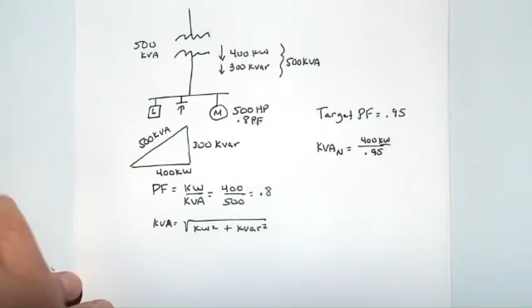My actual new kVA then, kVA new, would be my existing kilowatts, which is 400, because my kilowatts aren't going to change. Those have to still come from the utility, divided by my target power factor, which is 0.95. So if I do that, I take 400 divided by 0.95 and end up with 421 kVA. That's going to be my new kVA, and that's what I'm going to shoot for by adding a capacitor in. So how do I size that capacitor?